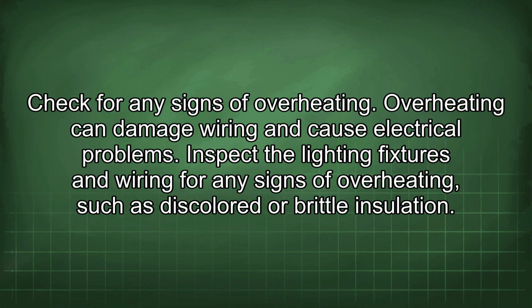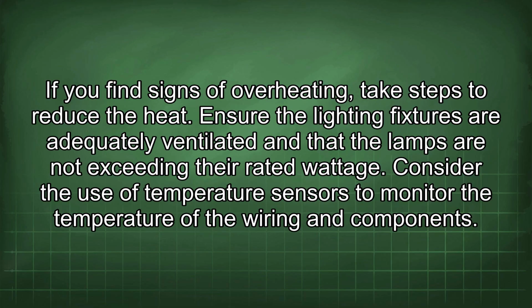Check for any signs of overheating. Overheating can damage wiring and cause electrical problems. Inspect the lighting fixtures and wiring for any signs of overheating, such as discolored or brittle insulation. If you find signs of overheating, take steps to reduce the heat. Ensure the lighting fixtures are adequately ventilated and that the lamps are not exceeding their rated wattage. Consider the use of temperature sensors to monitor the temperature of the wiring and components.